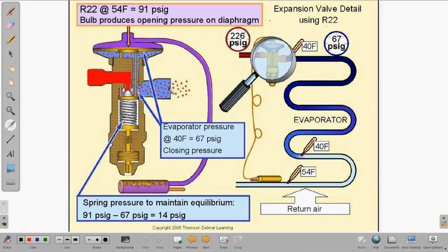So it is a temperature sensing device, and it will maintain a very stable superheat. The one thing is when you're checking pressures and temperatures with the TXV system, you need to allow 15 minutes for everything to stabilize, because at the start of the cycle, it's going to be hunting a little bit, so everything's going to move up and down until it reaches that equilibrium.